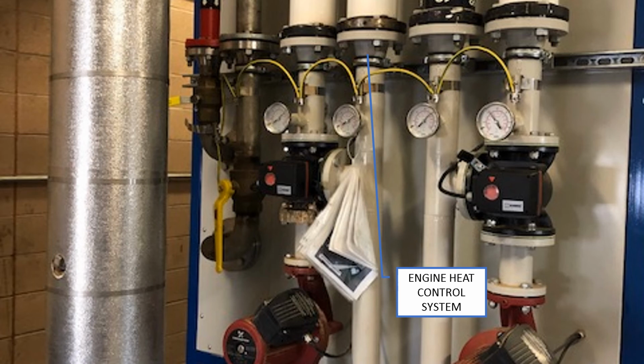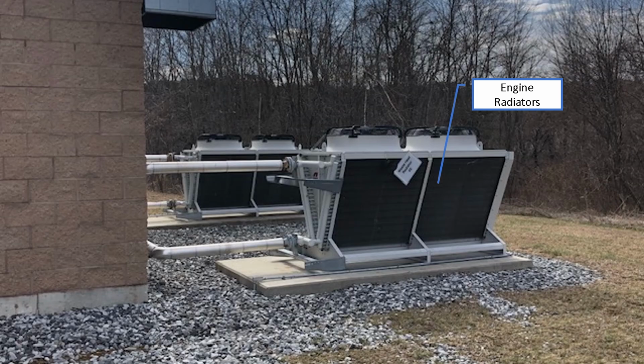The series of pumps and valves on the front of the cogen units are automatic controls telling whether or not there's enough capacity within our heating loop to absorb the heat from the engines. So if the water is cool enough, it can soak up some heat from the engines and send it back to the digester equipment building. And if it's too hot, this is where it gets diverted into a radiator. These are the engine radiators. Ideally, we do not use these cooling devices. Instead, we try to keep all the heat for the digestion process, as well as heating the spaces within the gas conditioning and the digester equipment building.